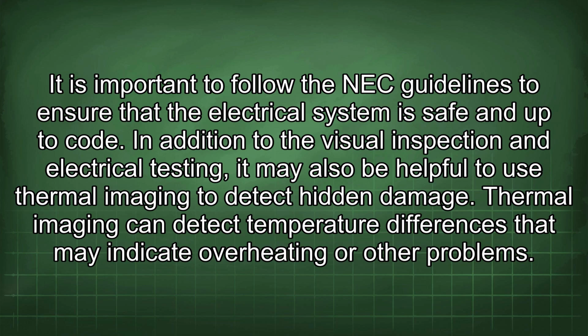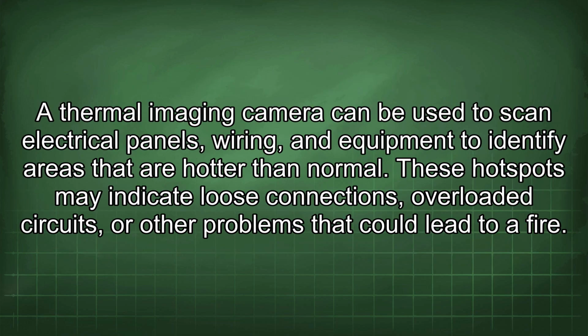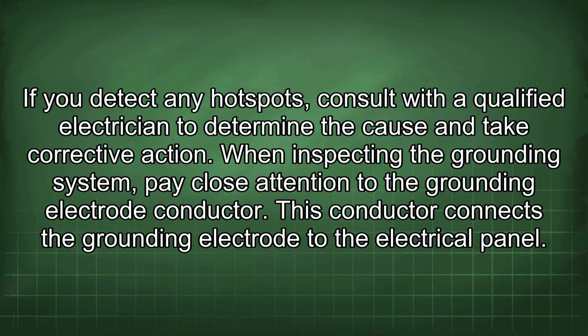In addition to the visual inspection and electrical testing, it may also be helpful to use thermal imaging to detect hidden damage. Thermal imaging can detect temperature differences that may indicate overheating or other problems. A thermal imaging camera can be used to scan electrical panels, wiring, and equipment to identify areas that are hotter than normal. These hotspots may indicate loose connections, overloaded circuits, or other problems that could lead to a fire. If you detect any hotspots, consult with a qualified electrician to determine the cause and take corrective action.